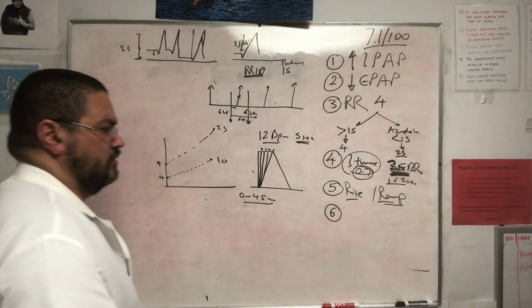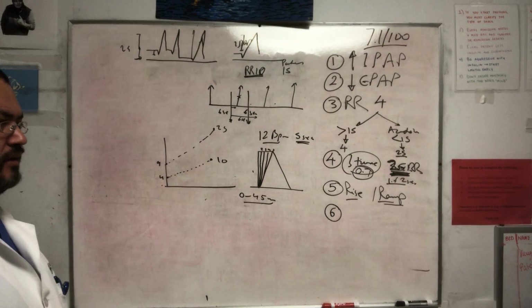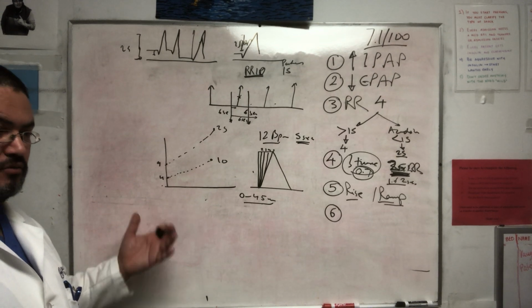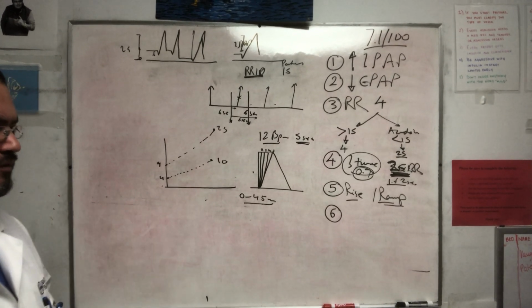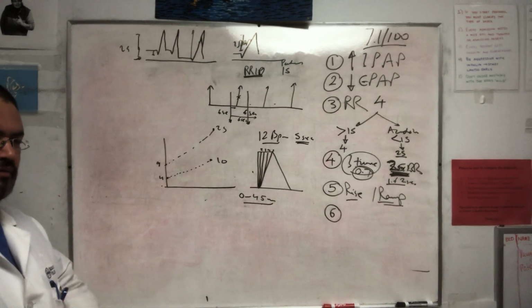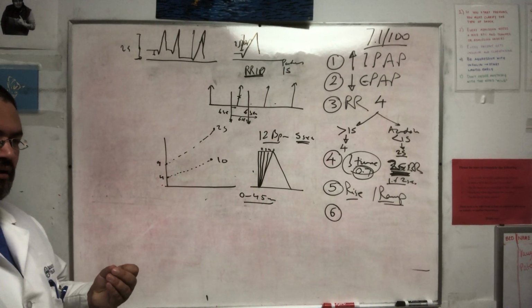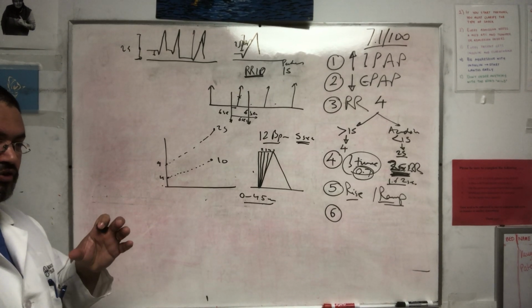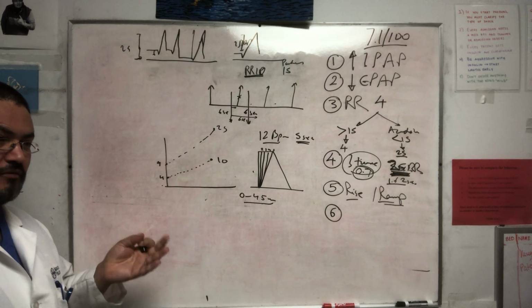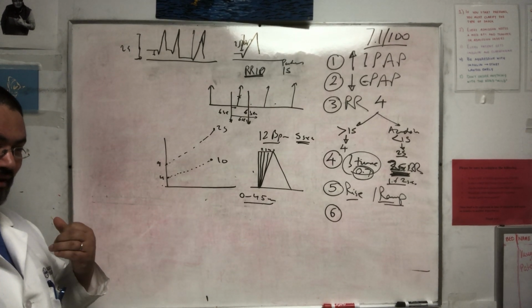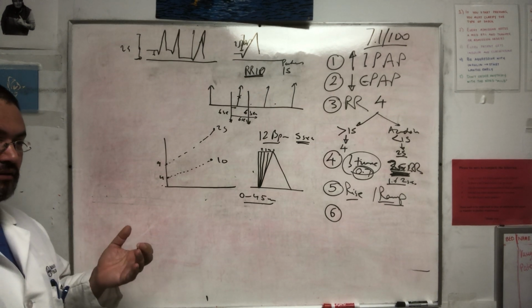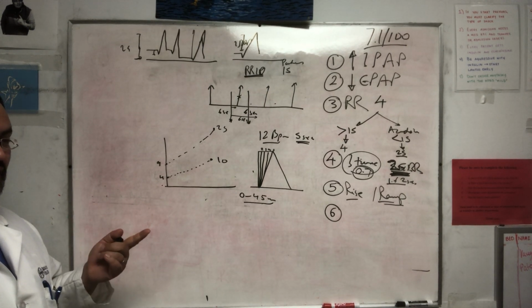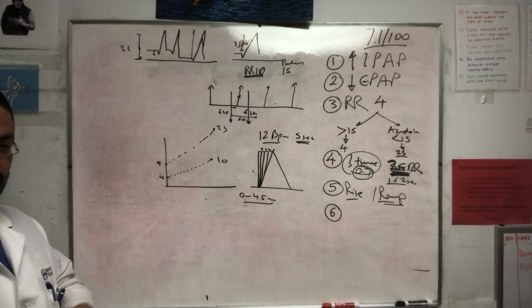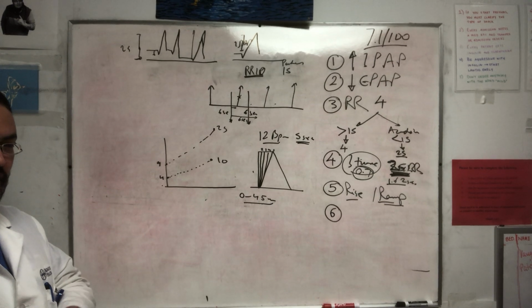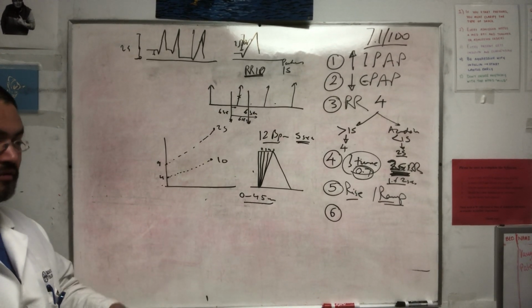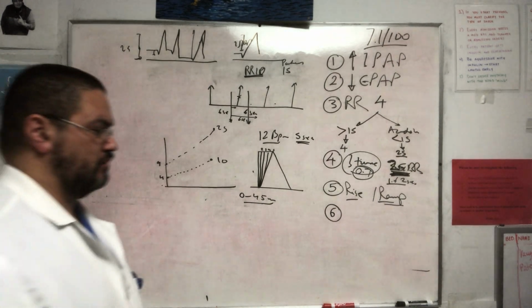Number 6. Again, by the way, there's also a BiPAP that they use in a small number of hospitals that actually senses your diaphragmatic movement. Because if the patient swallows, the machine receives that as a negative pressure, but it's not a negative pressure from the lung. You're doing like this, and the machine thinks that it needs to trigger the BiPAP. In those other vents, they add an additional thing. They have an electrode over the diaphragm, and they actually record the diaphragmatic movements. So when the diaphragm moves, the machine will give you the breath, which is much better, much more comfortable.